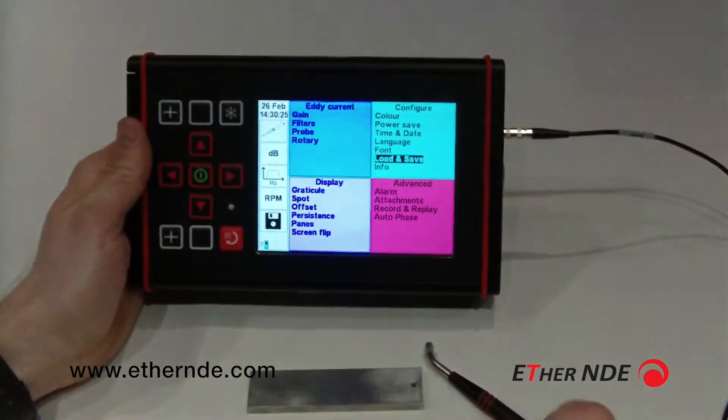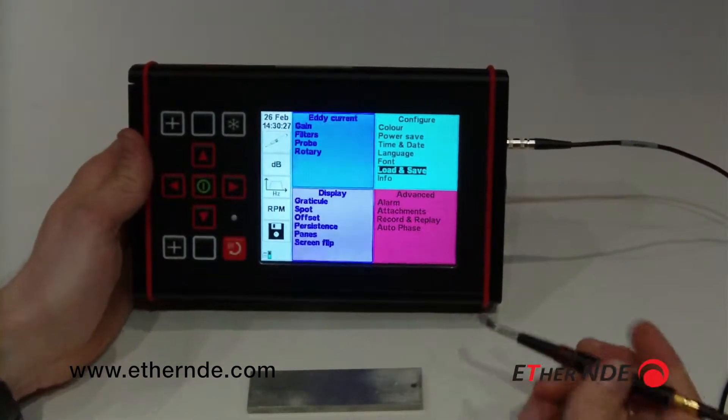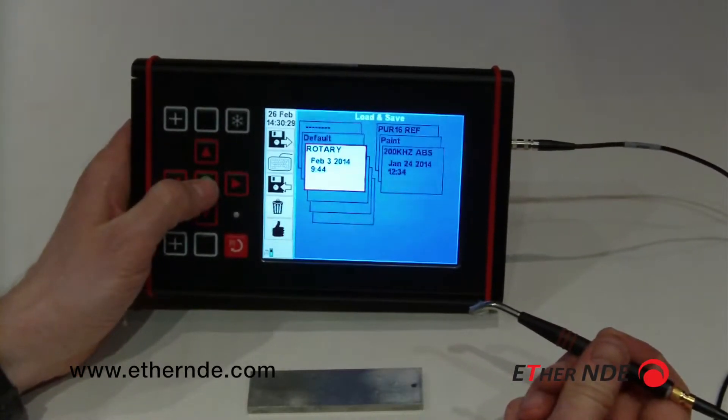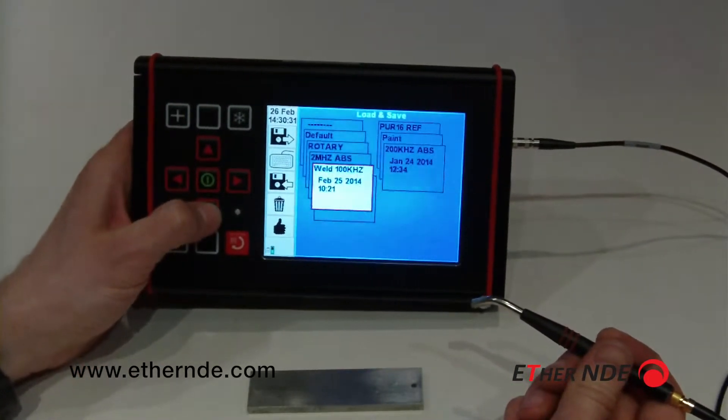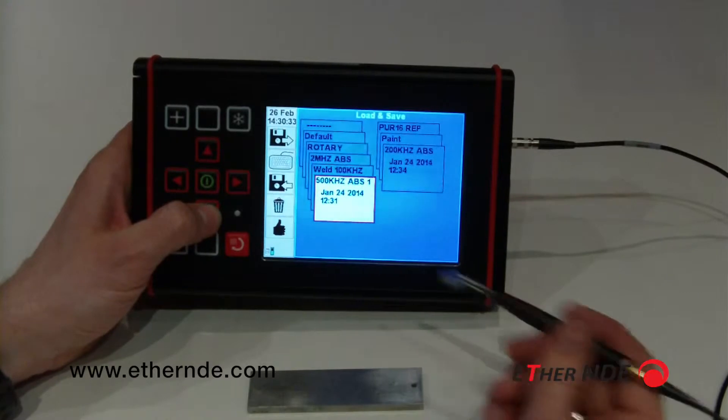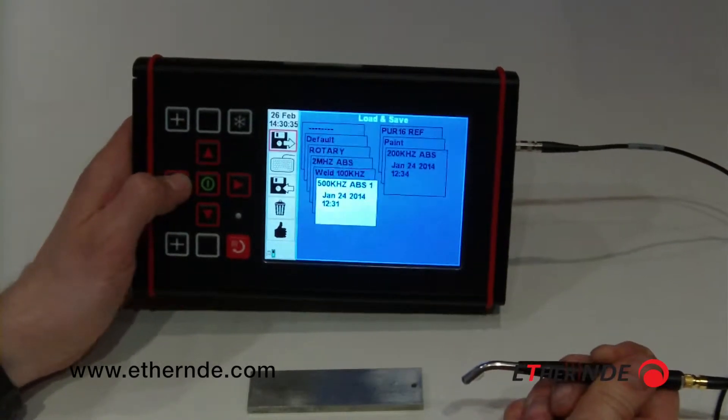I already have a setting stored on the instrument which is good for this probe. I'm going to go to load and save. I have a 500kHz absolute probe, I shall load that in.